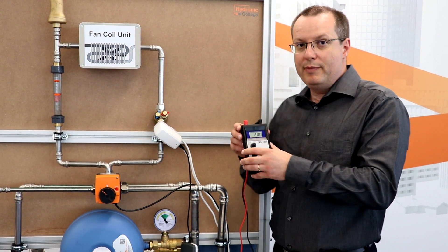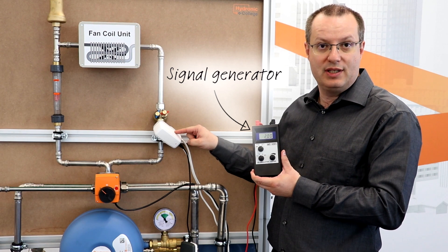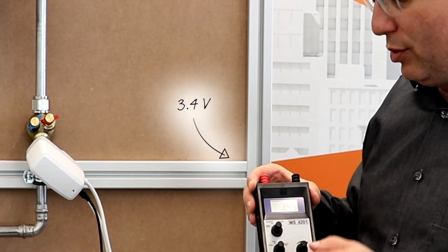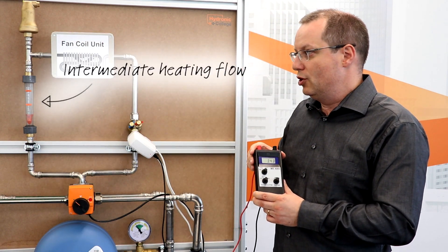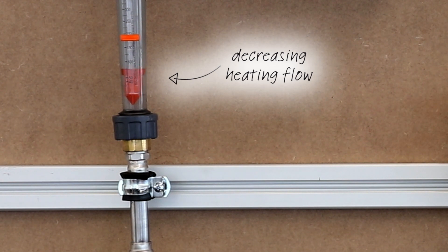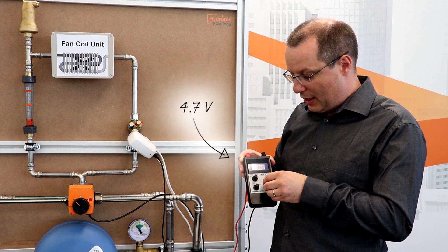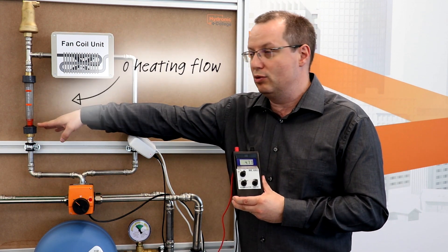I am now going to operate the changeover system. I'm making use of a signal generator to provide a 2 to 10 volt signal to the TA slider 160 plus actuator. If I increase the voltage to about 3.4 volts, we can see that the actuator is proportionally controlling the flow so that we get to intermediate values. The higher I increase the voltage to the slider actuator, the less flow I will get — up to a value of 4.7 volts where we should get basically no heating flow. Going to 4.7 volts just like here, you can see indeed that we get to zero flow in heat.